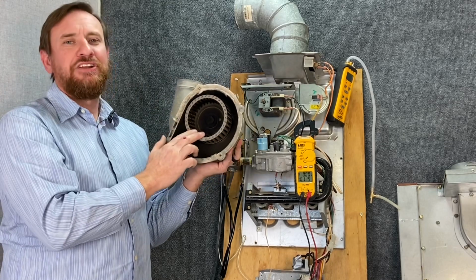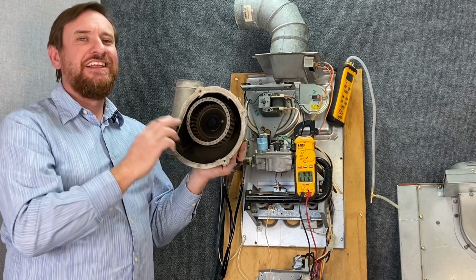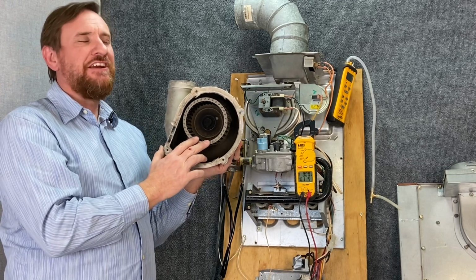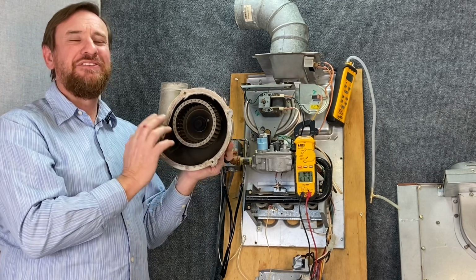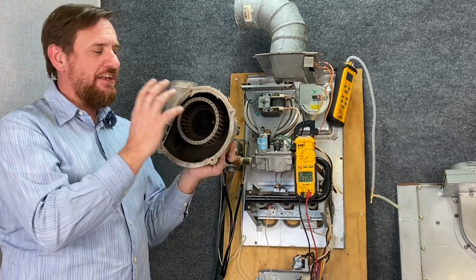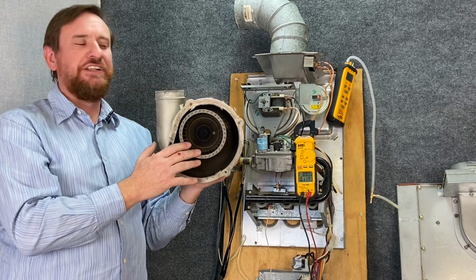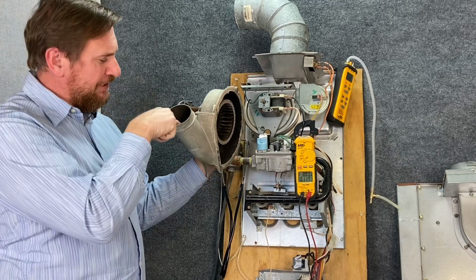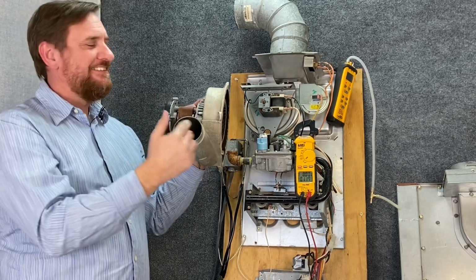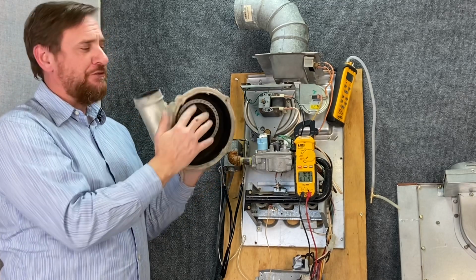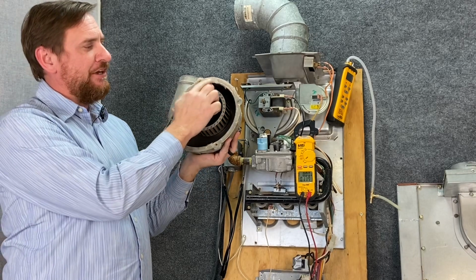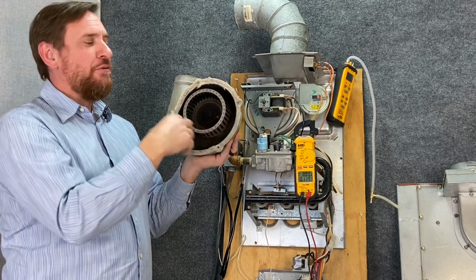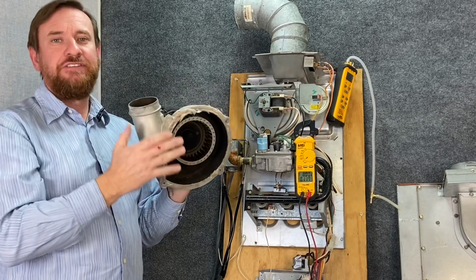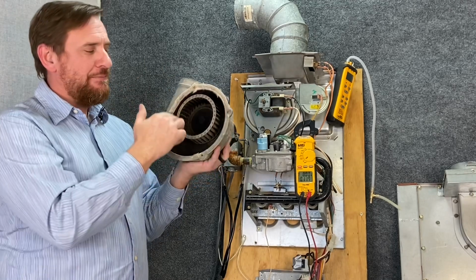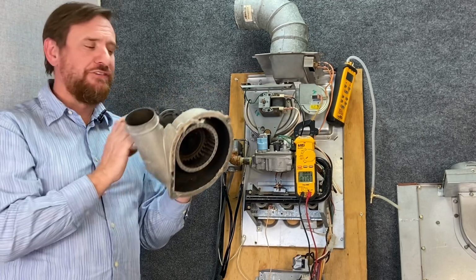But the problem is it also sooted up inside the heat exchanger. That's not covered under warranty. It's very difficult to clean that out, and you probably will never get it back to factory conditions. So it essentially killed this gas furnace. If we look through the tube on the end, we can see all of the black inside of the blower wheel without having to fully remove it. If you can see this one, we ended up with a lot of gasket material left over, which means once this was pulled off, that gasket would have to be replaced, but in this case, it's most likely going to be a new furnace.